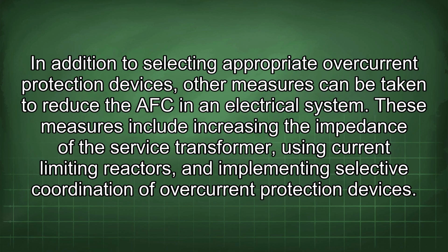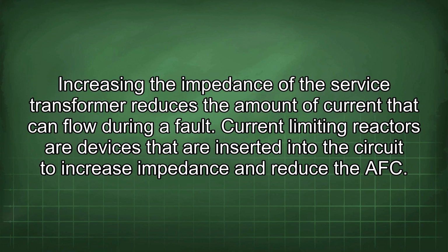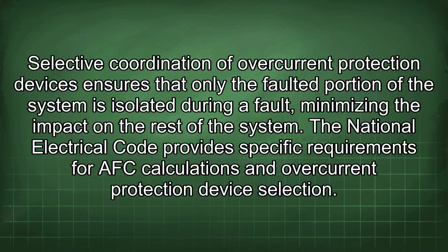In addition to selecting appropriate overcurrent protection devices, other measures can be taken to reduce the AFC in an electrical system. These measures include increasing the impedance of the service transformer, using current-limiting reactors, and implementing selective coordination of overcurrent protection devices. Increasing the impedance of the service transformer reduces the amount of current that can flow during a fault. Current-limiting reactors are devices that are inserted into the circuit to increase impedance and reduce the AFC. Selective coordination of overcurrent protection devices ensures that only the faulted portion of the system is isolated during a fault, minimizing the impact on the rest of the system.